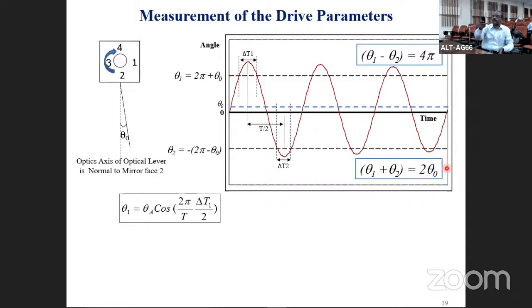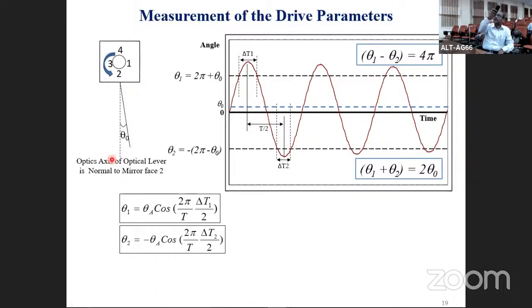Similarly, if you reverse, you go back and again hit. So you're coming back from here. Now you're coming to this optical lever before it hits the 2 pi. So it is 2 pi minus theta 0. So you got theta 1, you got theta 2. What you do is theta 1 minus theta 2, and what you get is 4 pi. And if you do theta 1 plus theta 2, you get 2 theta 0, which is the offset. So all you have to do is substitute values for theta 1 and theta 2.